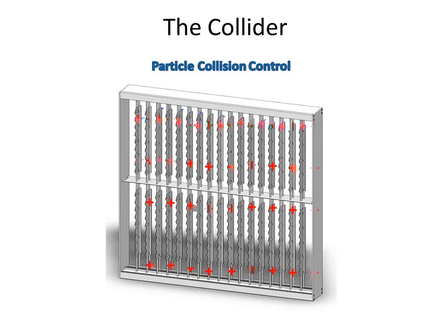This is a picture of the collider. You can see right through the collider. It has virtually no pressure drop. It's like 0.05, and the airway length is about 4 inches. So you can use this by itself. It'll send neutral particles down to agglomerate airborne particles. And this does just work on airborne particles. It doesn't draw a whole lot of power. It's about 100 watts per 60 square foot.